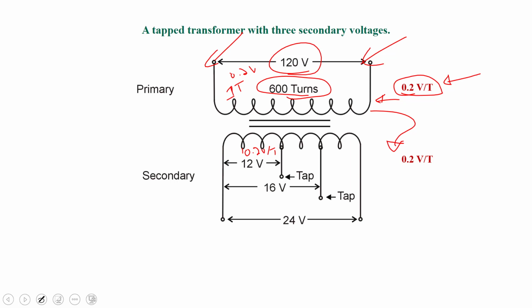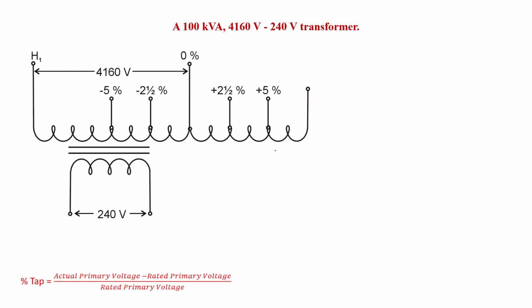Now when we're talking about distribution transformers, that's a little bit different. So when we look at a transformer for distribution, we can also have tap transformers there. And we have it here because we are trying to get the correct secondary voltage. So let's say that my building has a 4160 down to 240 volt transformer. The loads I connect in my building are all rated at 240 volts. I do a light bulb, maybe I've got a 240 volt motor or something like that, right? And they run best at 240 volts.